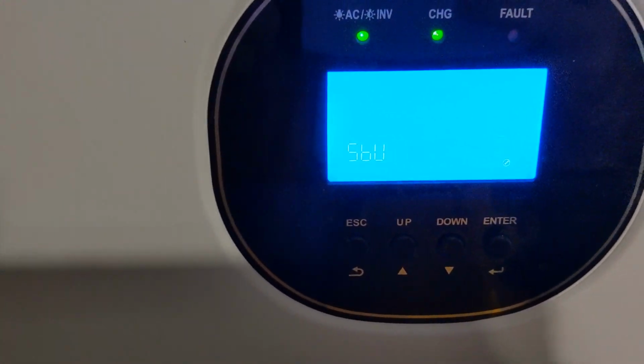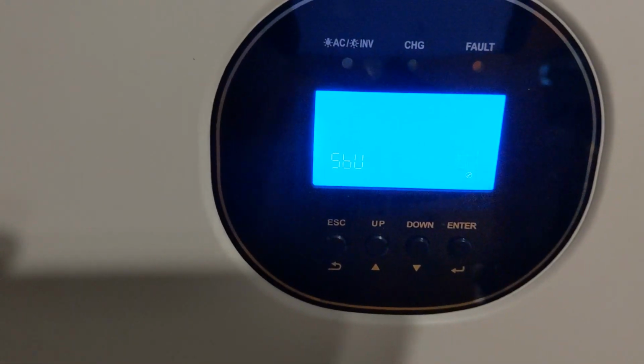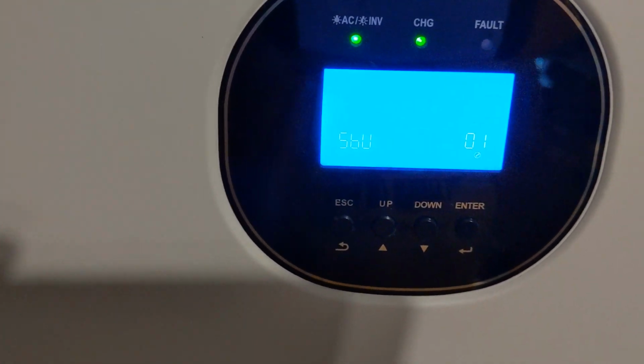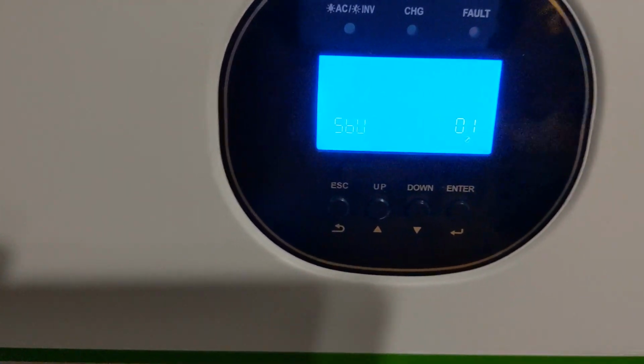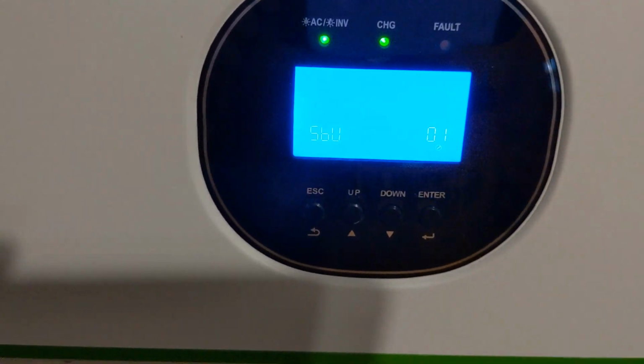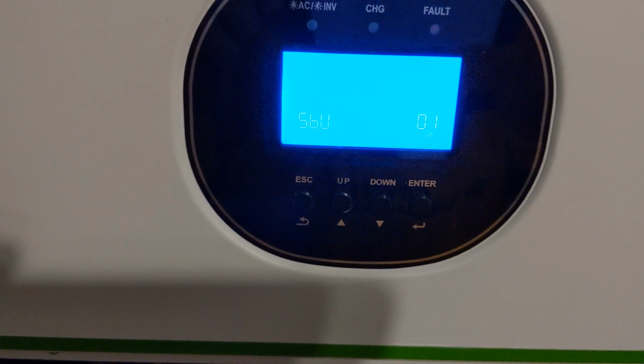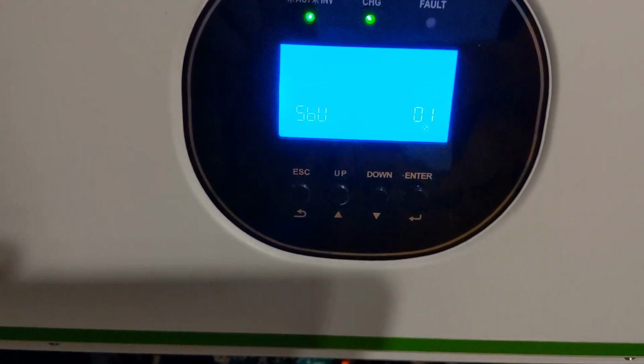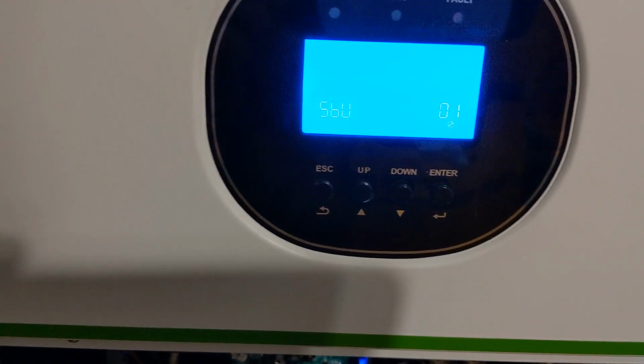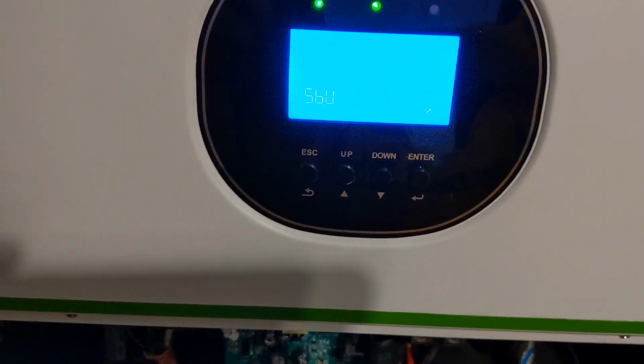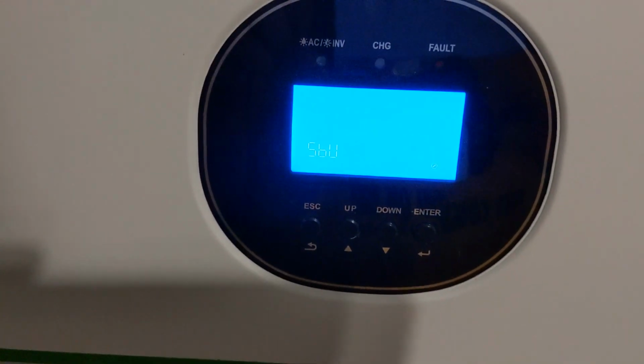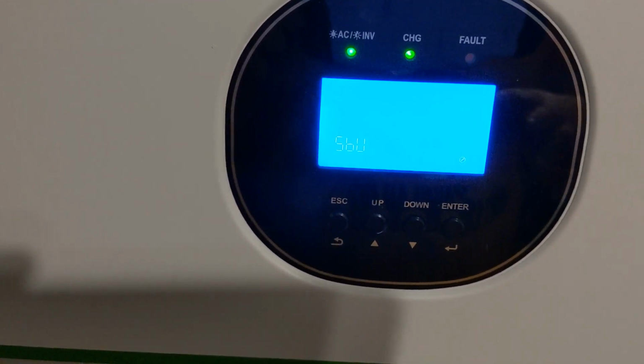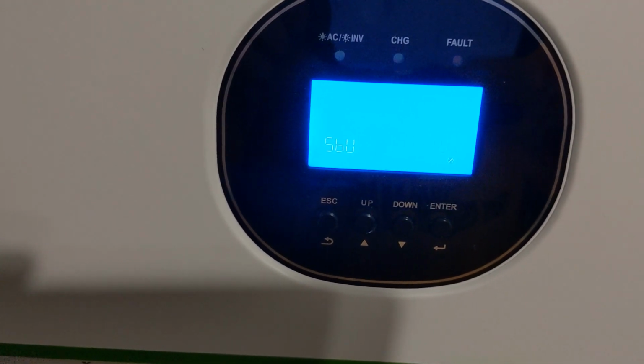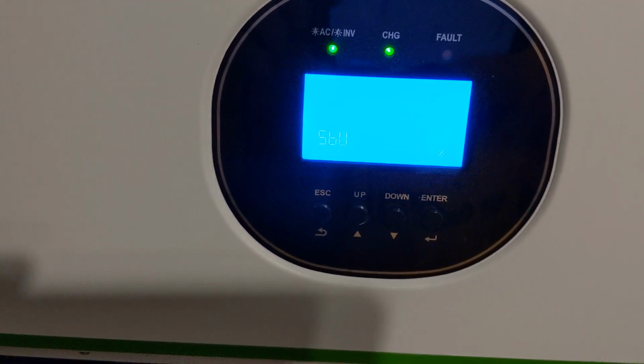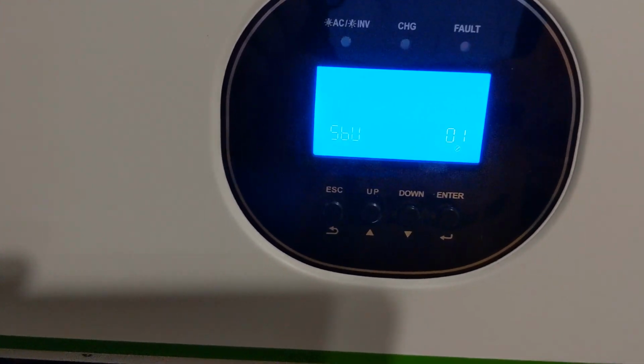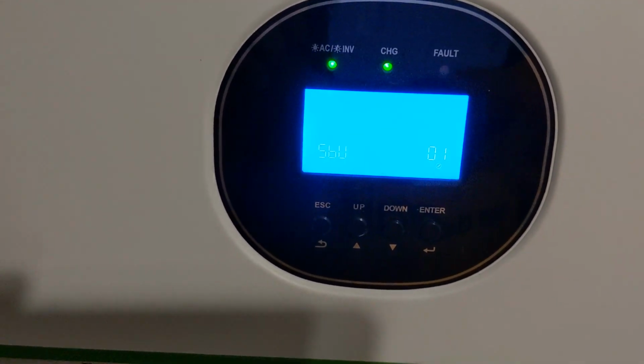I have mine set on SBU. That basically means it's going to power things based on solar and battery, and then utility last. So as long as there's enough solar to keep everything charged up and the batteries stay above the voltage cutoff point I've set, it'll stay on solar and battery mode. If it drops below the low voltage limit I've set for the battery, then it'll switch back to the grid. The switch is pretty much instantaneous, it happens very seamlessly — I don't think I've ever even noticed anything flicker when doing it, and then it switches back and forth.